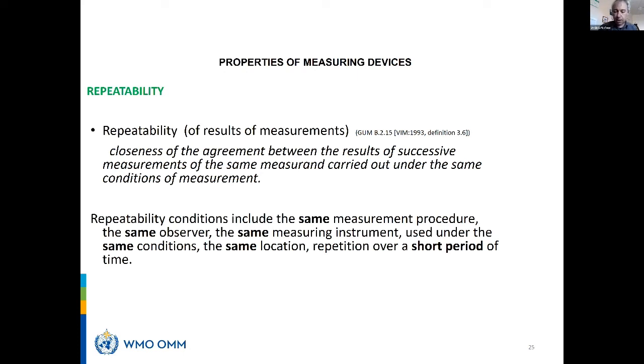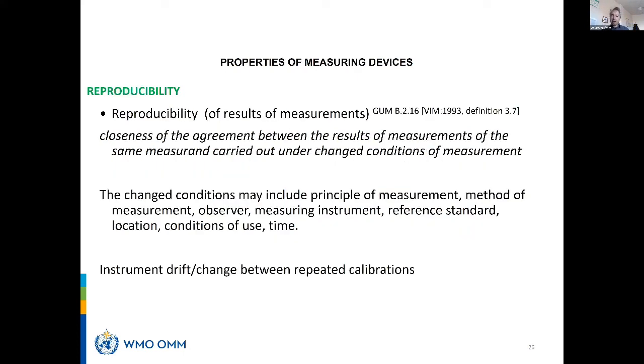And then we have reproducibility, which is a little different. It's the closeness of agreement between results of the same measurement carried out under changed conditions. For example, reproducibility is if I call my colleague and say please do this measurement - using the same instrument and procedure, measuring the same thing, but the person is different.